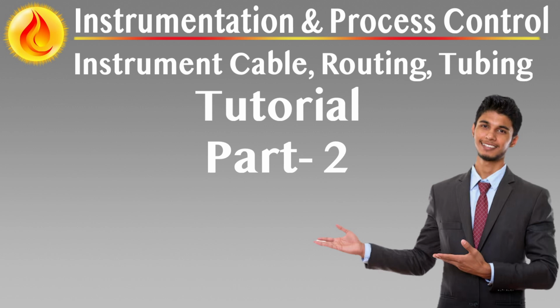Earthing connections for signal cables. Instrument signal cable screens must be earthed using the star point method, ensuring that each screen is connected to instrument earth at one and only one location. Screens must be electrically insulated from cable armor, equipment enclosures, and support structures to prevent ground loops.